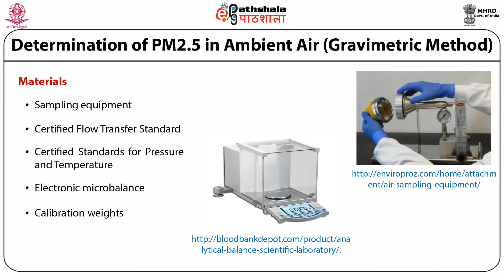The calibration weights utilized as mass reference standards should be non-corroding, range in weight from 100 mg to 200 mg, and be certified as traceable to NIST mass standard. That NIST is known as National Institute of Standards and Technology. The weights should be ASTM class 1, where ASTM stands for American Society for Testing and Materials, and class 1 category with a tolerance of 0.025 milligram. Non-serrated forceps are used for handling filters.